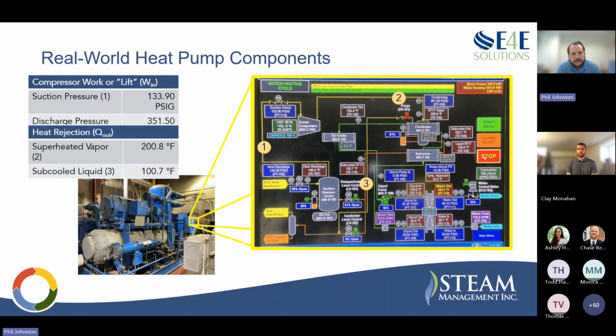So when looking at a heat pump, Clay already went over this, but what's really driving performance is the work that the compressor is doing and the heat that's being rejected. That's how you evaluate the performance. In this real life scenario, we have a few points that show how this heat pump is performing. You have the suction pressure and discharge pressure across that screw compressor, so that's the pressure being added by the compressor. Once that high pressure vapor, which is superheated, which is just a fancy way of saying it's much hotter than a saturated condition, or basically has more heat in it than normal, goes through the condenser, it rejects all the heat. So we go from 200 degrees before the condenser to 100 degrees. That's quite a bit of heat we're rejecting through the condenser.